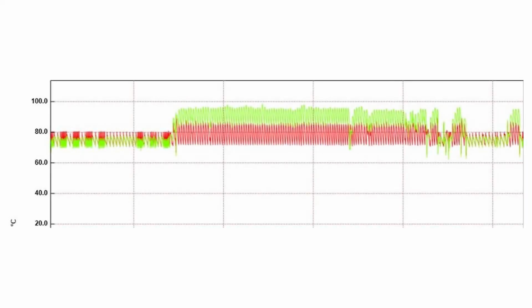You can see on the initial data here 3 data sets. The first one where the boiler is running reasonably well, a decent flow and return, and although it's cycling quite a lot, with a lot of on and offs, it's reaching temperature and offering decent heat to the building.